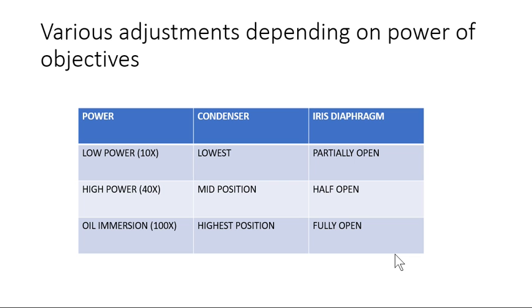Let's recap. With low power, the condenser should be at lowest position and iris diaphragm partially open. With high power, condenser at mid position and iris diaphragm half open. For oil immersion, condenser at highest position and iris diaphragm fully open—this is maximum illumination.